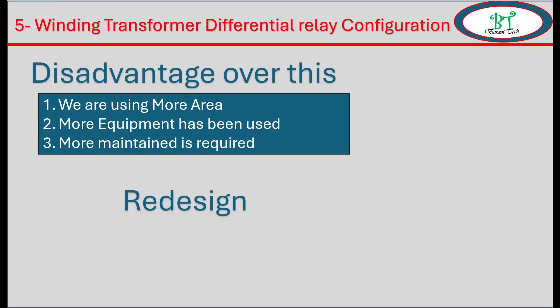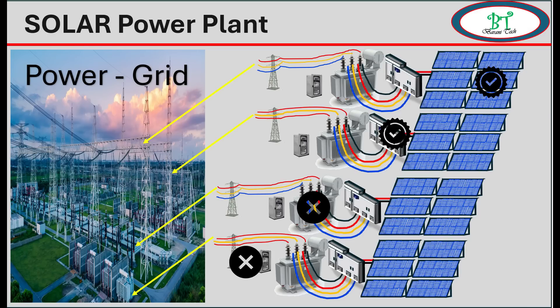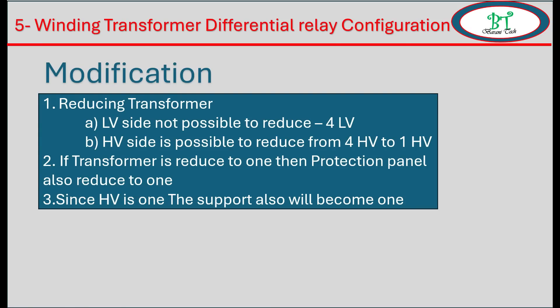Now we will try to redesign the system. Reducing the solar panel is not possible since we need the power it generates. Making one power module a bigger size would be very costly, but we can integrate multiple power modules into one single structure. For the power transformer, we can reduce four two-winding transformers into one transformer with one HV side and four windings on the LV side.